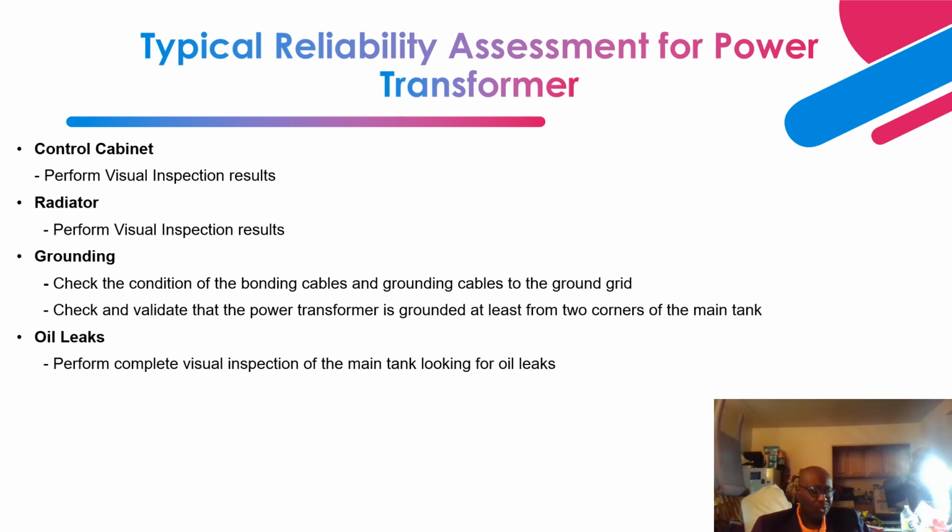And for bigger transformers, I've also seen about 4 grounding cables. Right? So it depends on the grounding philosophy that the utility company is implementing, and also on splitting the ground currents. Because as you add more grounding cables, you're providing a much lower resistance to the ground grid.